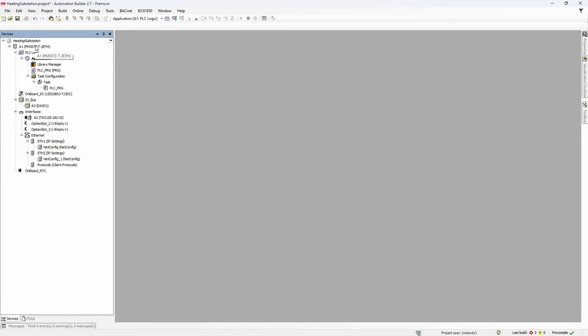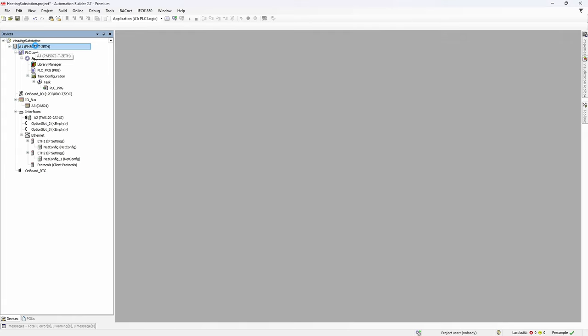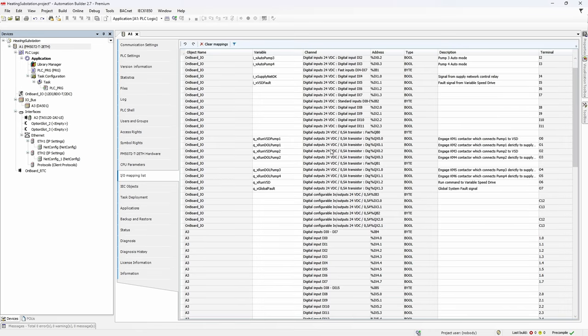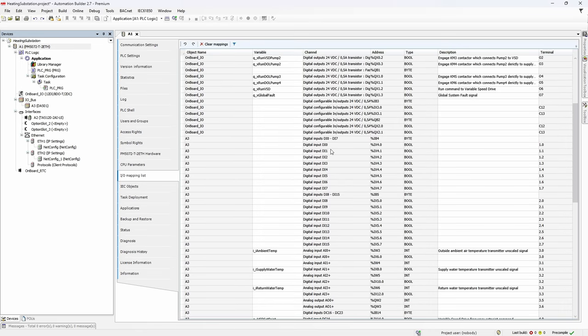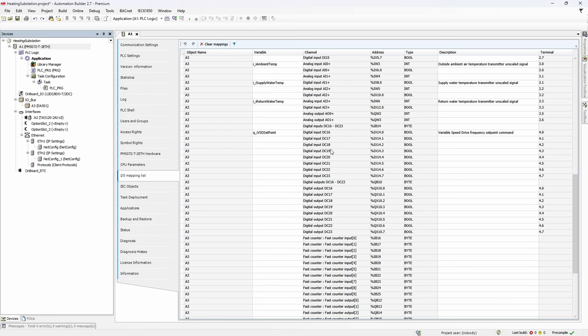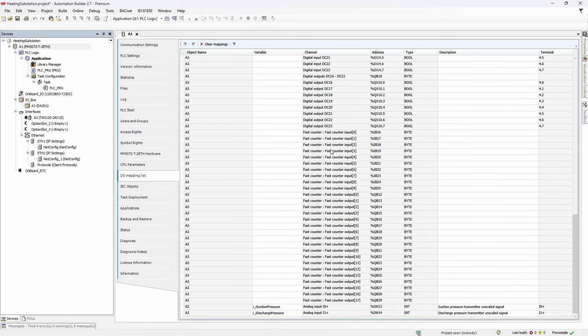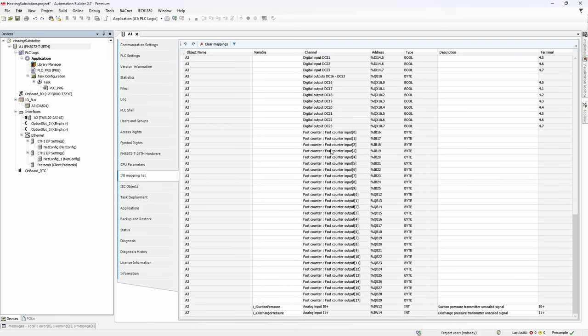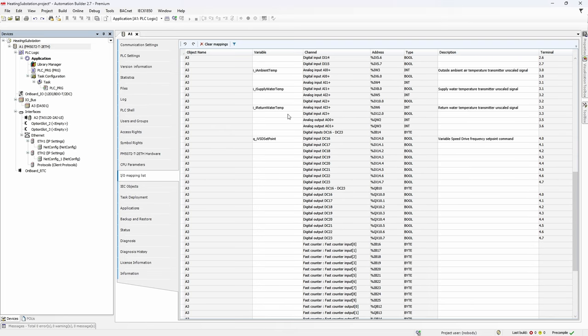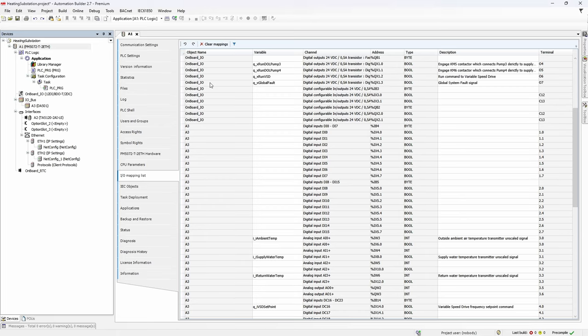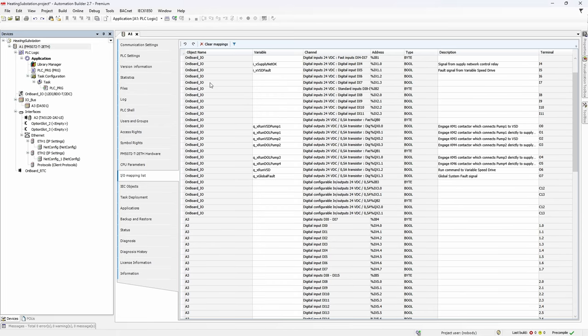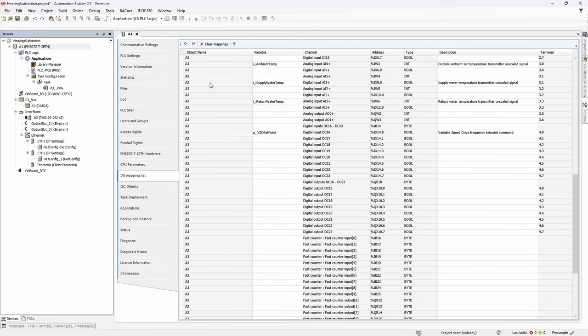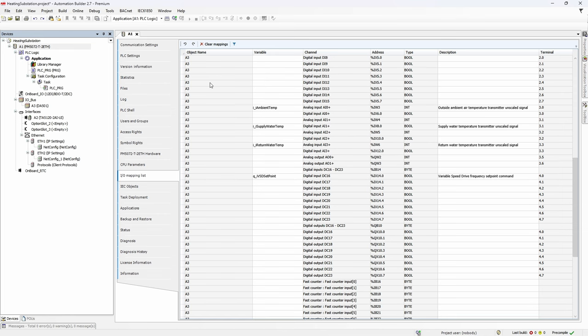If we go to PLC settings, find IO mapping list tab, we can see all inputs and outputs of the PLC in one flat list. If you're asking is it possible to pull the same trick with Excel here, the answer is yes indeed. You can do all IO mapping preparation in Excel and then just paste it into Automation Builder in one shot. I will leave the link to this spreadsheet in the description section below the video so you can try it yourself. I will also leave the link to the project file so you can follow along.